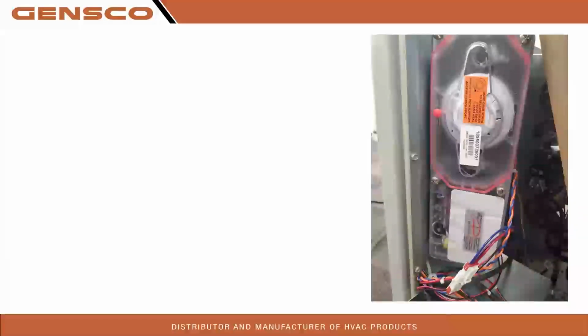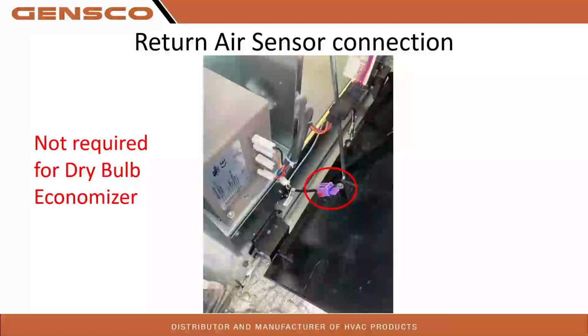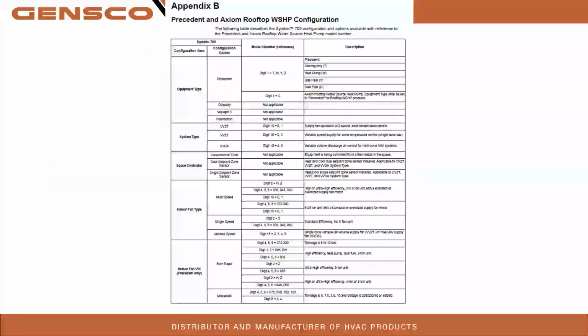There's our factory smoke installed. Return air sensor connection. We get a lot of calls on this. This is right by the actuator for the economizer. That is a return air thermistor. That is not required for dry bulb economizer, so there's nowhere to plug it in. Nowhere to read it, just so you know. That comes, you're going to use that with the comparative enthalpy. This is Appendix B. I can send you.